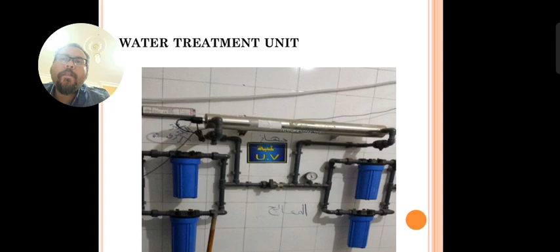This is the RO, the reverse osmosis part. From this reverse osmosis we can assess the water treatment capacity of this unit. This RO has three membranes, 1, 2 and 3. Every RO membrane can serve about 7 to 8 hemodialysis machines, so this water treatment unit can serve about 24 hemodialysis machines.